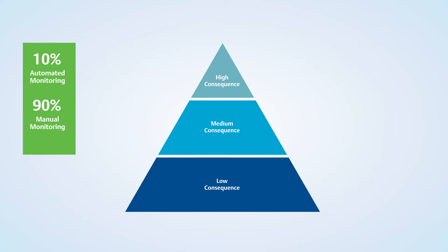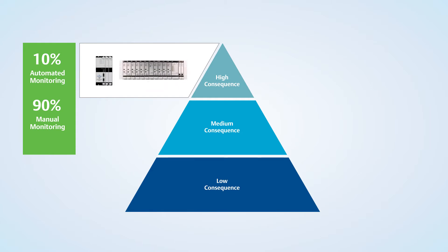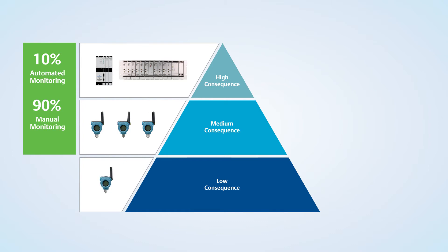Today, 90% of total assets are monitored manually, meaning the data collected must be reviewed by a vibration analyst to diagnose developing issues. The criticality of the asset determines how it will be monitored. The most critical and most expensive to replace are monitored using online rack-mounted systems that provide continuous protection capabilities. The balance of plant assets is monitored using either wireless devices for economical continuous monitoring or handheld instruments used to collect data on calendar-based routes.